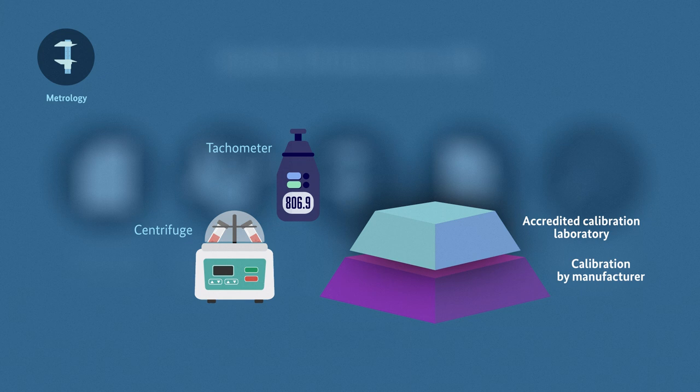The tachometer needs to be calibrated as well, of course, and compared to another reference device on a regular basis. This is done by an accredited calibration lab.